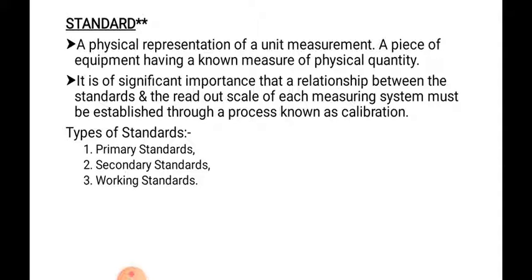Means out of that, 20 grams will be worn out because of the continuous use of those weights over longer years. So that's why it must be calibrated every year. And for increasing the weight up to 1 kg, some 20 grams of external weight is attached, it may be copper or brass, to the top portion of the weight. I think you might have observed.